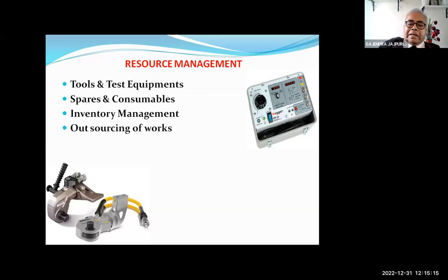Tools and test equipment also need calibration as per ISO requirements, depending on the size of the industry. Some level is awarded to test equipment - level 1, level 2, level 3. Level 1 is very accurate equipment, and that calibration has to be done from an NABL accredited laboratory, depending on the size of the industry, or they can ensure from the outsourced agency whether their test equipment is calibrated from NABL or not, through a contract condition.